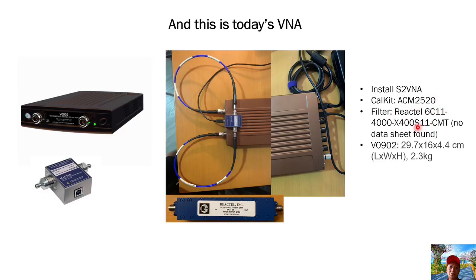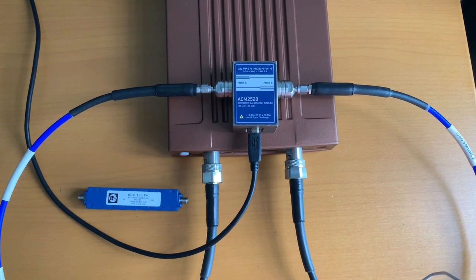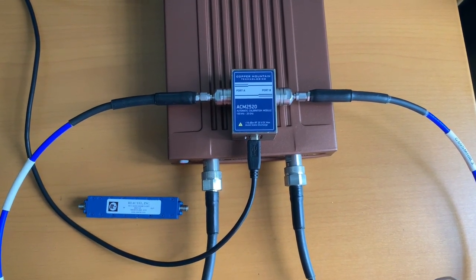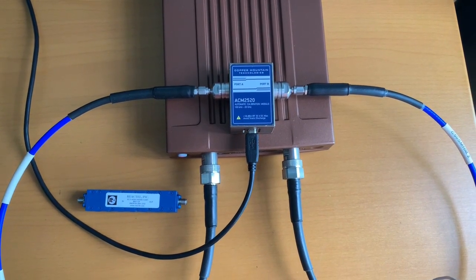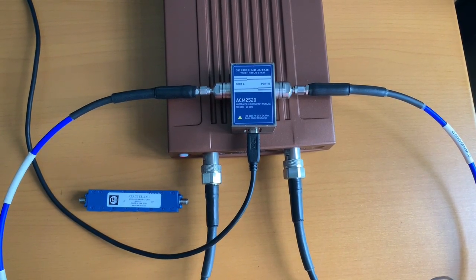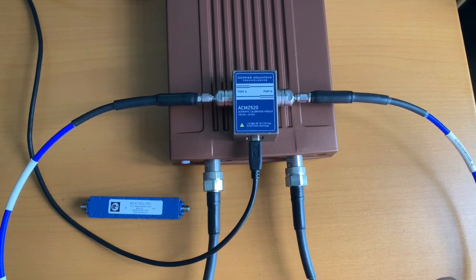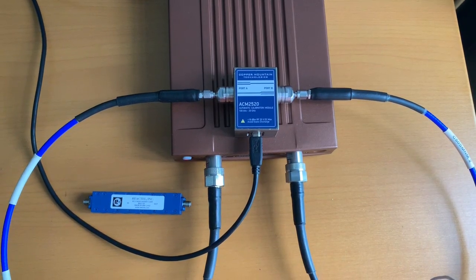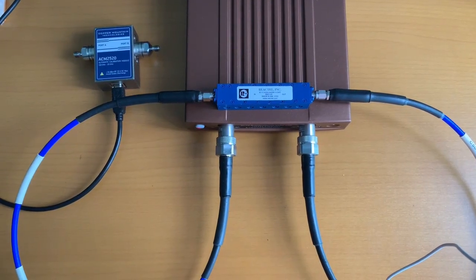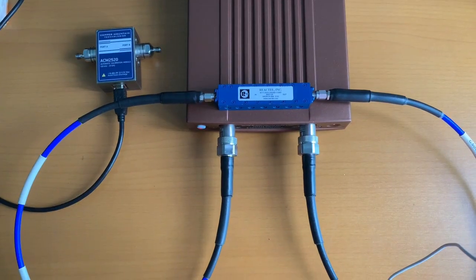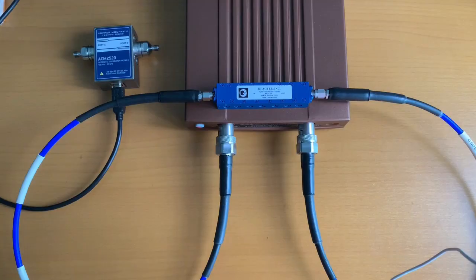The filter's model name is very long, but I couldn't find the data sheet on the website. So I don't know how to do the calibration for this testing before I know the operation frequency. So what I'm going to do is conduct a function test for the filter first. By right, I should conduct the automatic calibration first, but since I couldn't find the specification of the filter, I will skip the calibration first and conduct the filter's function test to find out its operation frequency. So instead of connecting the ACM to the two ports of the VNA, I connected the filter to the two ports of the VNA to conduct the function test of this filter.